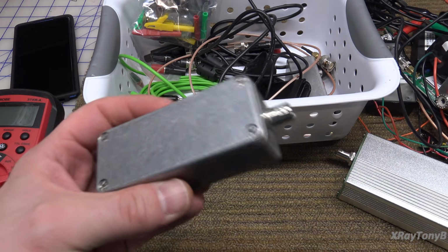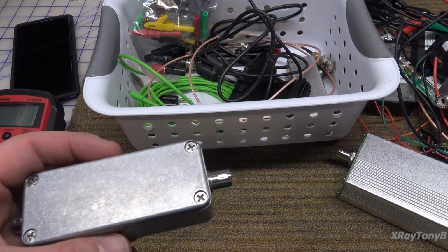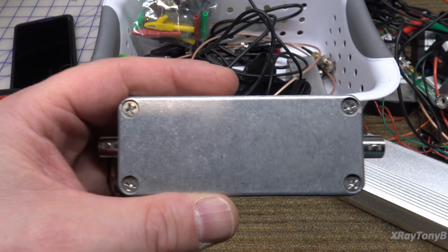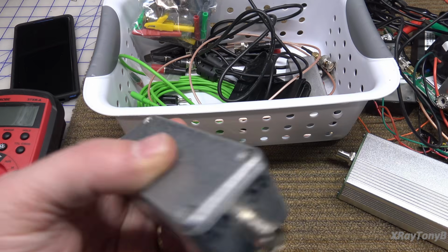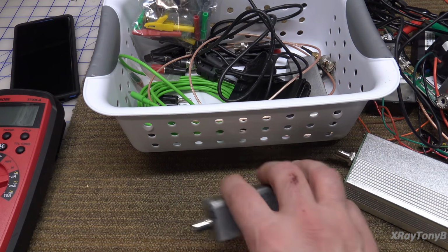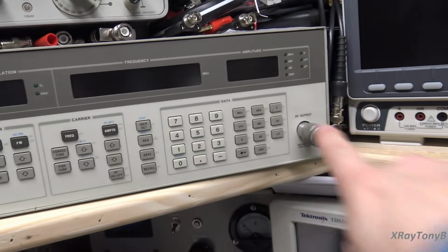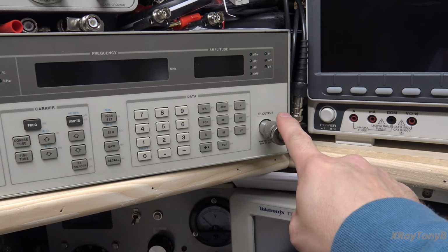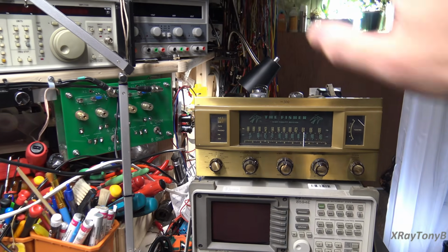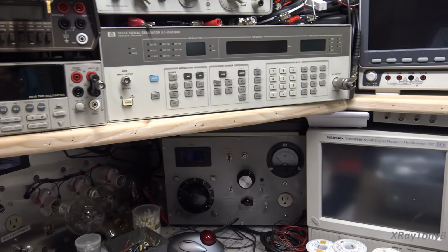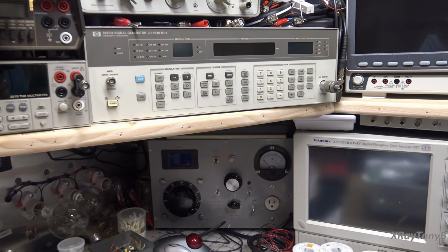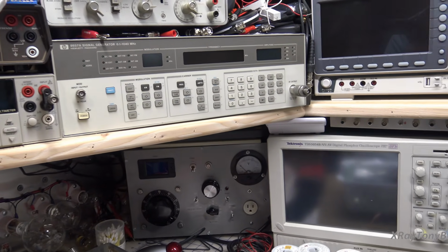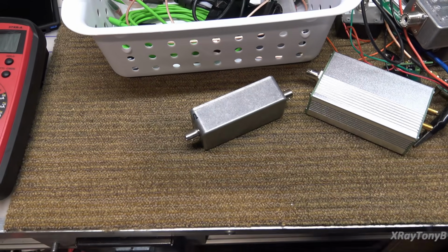This is something you've all seen when I did the video on how to connect a 50 ohm output to a non-50 ohm load, and we talked about impedance matching. So what this does is this lets you put your signal generator into here, because if you notice, for instance, the HP 8657, the output is relative to a 50 ohm impedance or a 50 ohm load. But most audio gear, like a receiver, will either have a 75 or a 300 ohm termination. So it'll give you a slight difference in amplitude. It's really not that big of a deal. But if you want super accuracy, if you're doing signal to noise and things like that, and you want as accurate a signal level as possible, you need to match the impedance. And that's what this does. This is just a little L network. And I've done a video on how to make this, I believe.